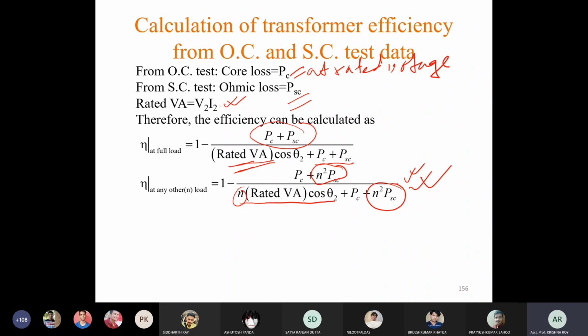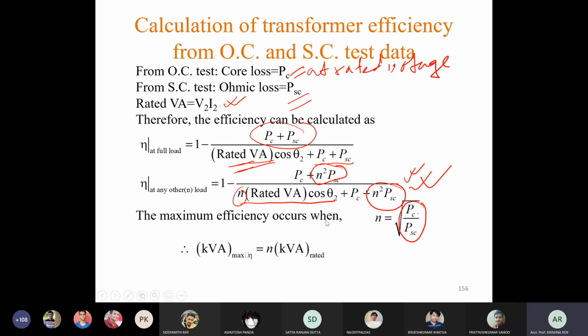Okay, and the maximum efficiency occurs when n equals root over PC by PSC. Both these are rated losses: PC rated core loss, PSC rated copper loss. And we know another relation, that the kVA load at maximum efficiency is equal to n into the kVA at rated load. So rated kVA into n will give you the kVA load at maximum efficiency.